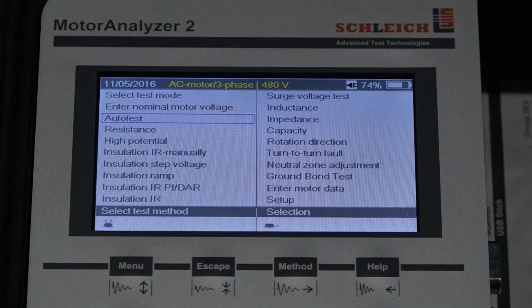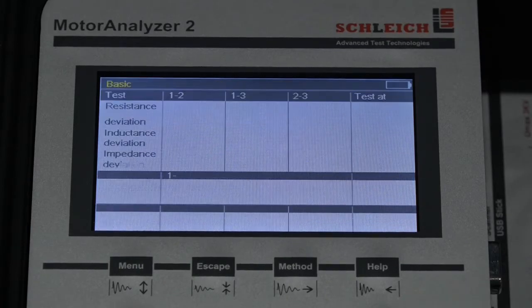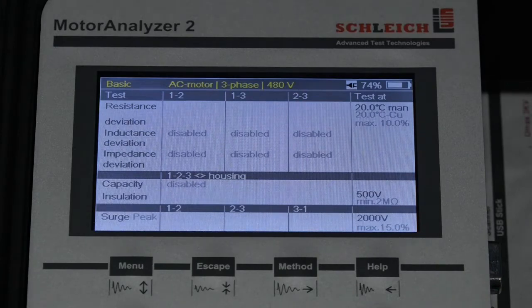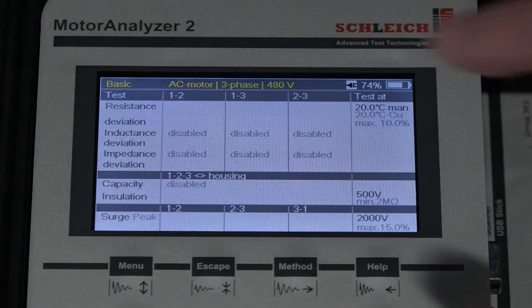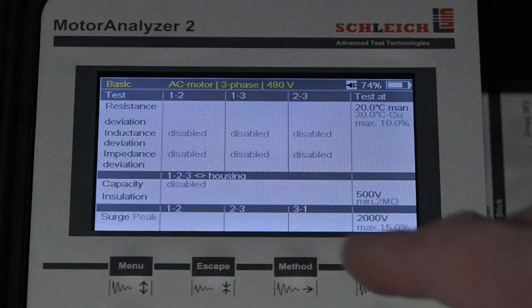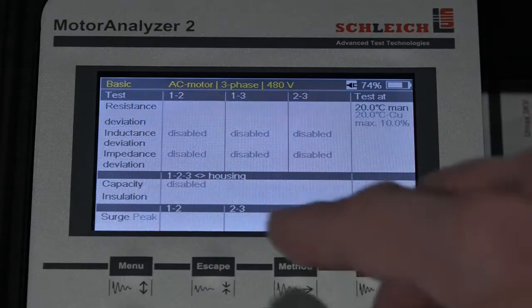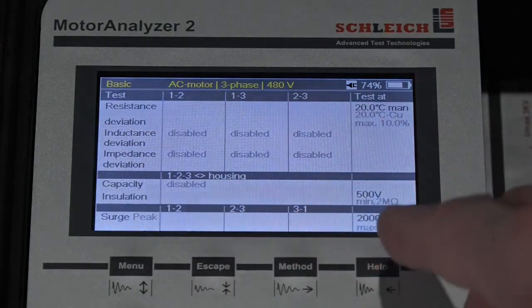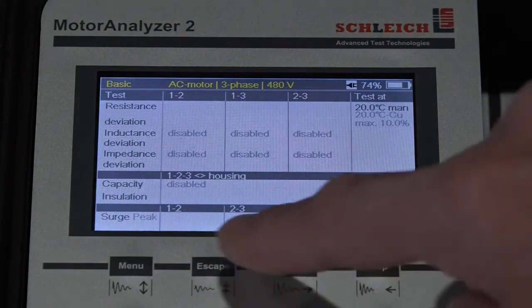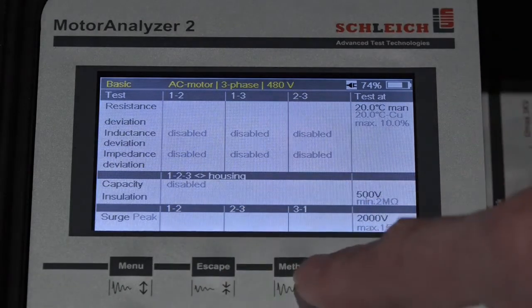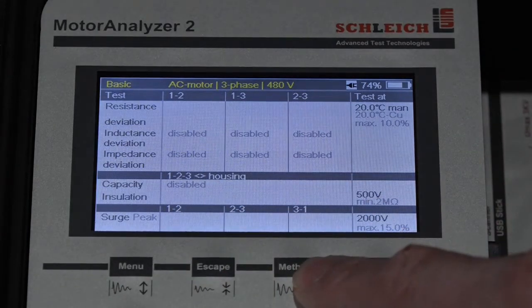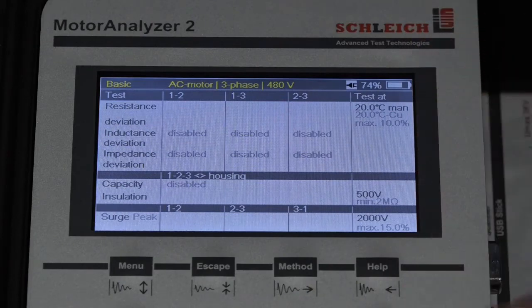Now that we have our test modes defined, let's go and look at the auto test screen. Here we have the test that we're going to perform. We'll have a resistance test. We've disabled some inductance and impedance tests. We've also disabled a capacitance test, and we'll jump right into an insulation resistance test at 500 volts. Then we'll step into a surge test. So when we press the start button, it's going to automatically go through all these tests that we have enabled. So let's just do that. Press the start button.